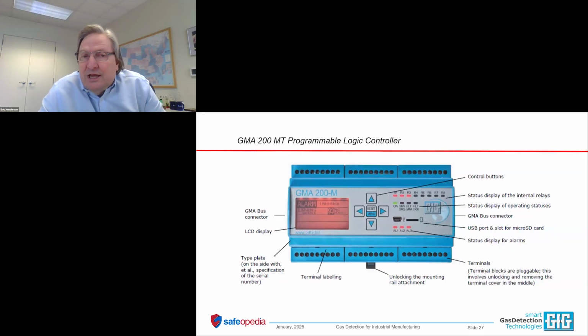Another type of controller is a PLC type controller, a programmable logic controller. Here, this is what we would call a DIN rail mounted design. A lot of your electronic control equipment at a manufacturing site is going to be mounted, everything from thermostats to gas detection controllers, on something that we call DIN rail. DIN rail looks like little miniature HO scaled railroad tracks. And you've got track after track mounted horizontally in a cabinet. And these are an industry standard size and format. And equipment like this particular controller sits nicely on the DIN rails. It makes wiring and mounting the equipment that much easier.